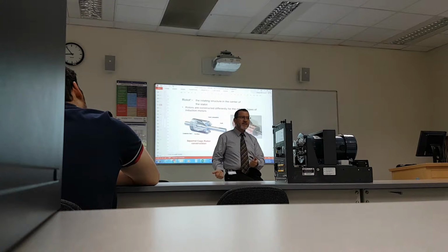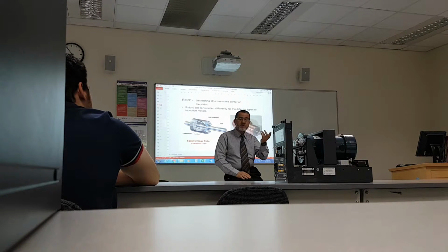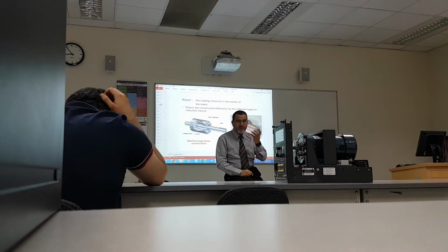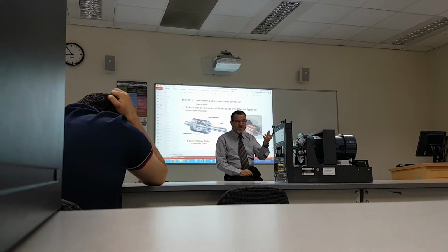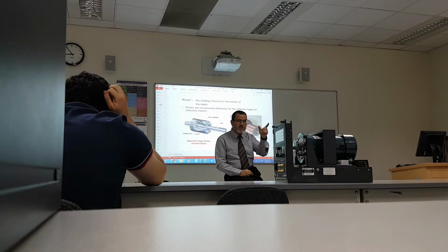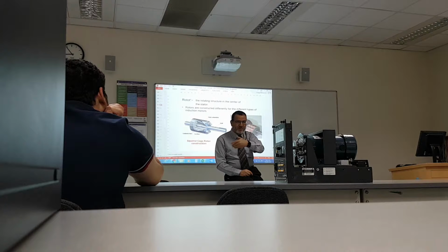But if you have the data, then you can see, okay, it costs us so much per year to pay for our power factor, which is 0.7. How much will it cost us to put in a synchronous motor or capacitor banks? You have to calculate first how much you need. How big is the capacitor bank or the synchronous motor? And then, how much is it going to cost? How much will the installation cost? How much is the maintenance? And then you have a yearly figure. How many years will it take to recover? Is it better to continue to pay Kahrama or to put in a capacitor bank?